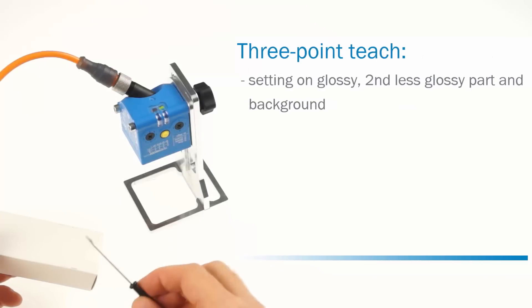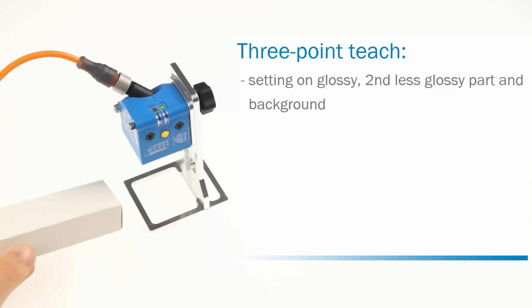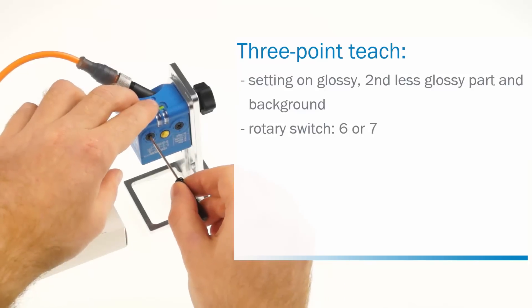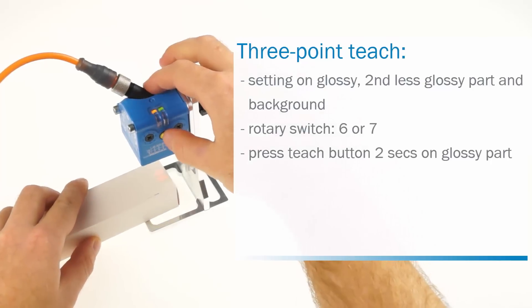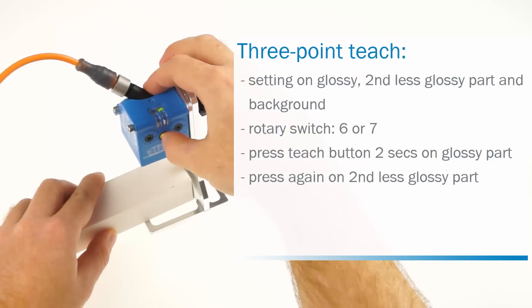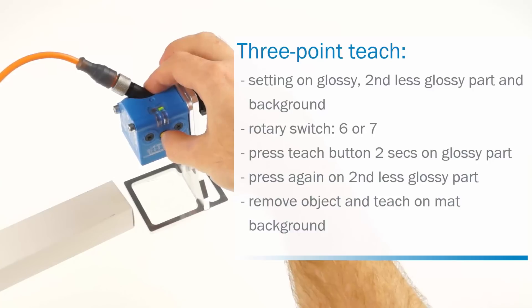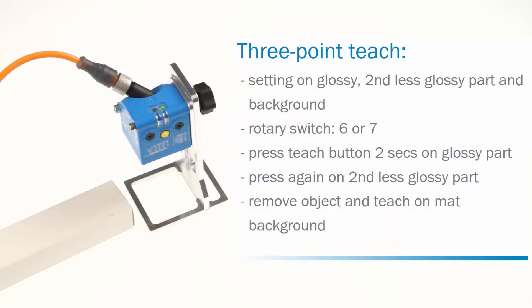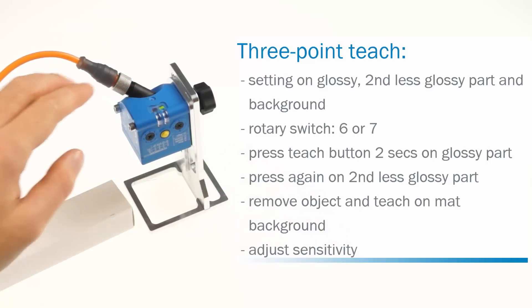The third method is the three point teach. This method requires adjustment on the glossy part that shall be detected, on the second less glossy part of the object, and a teach when no object is present. It is used for applications where an alarm in case of no detection of material is required. Set the rotary switch to six, or respectively seven for the inverted Q output. Move the glossy part under the light spot and press the teach button for two seconds. The yellow LED starts flashing. Then move the second less glossy part under the light spot and press the teach button again; the yellow LED keeps flashing. Finally, remove the object and press the teach button again when the sensor's light spot is located on the background. Please observe that the background shall be matte and not glossy. The sensitivity can be adjusted by setting the other rotary switch to A, B, or C.